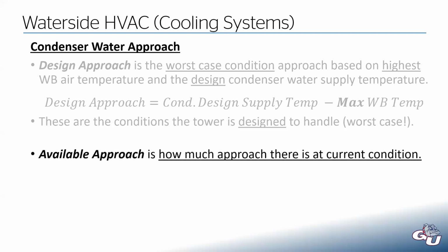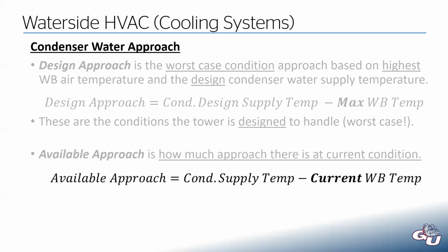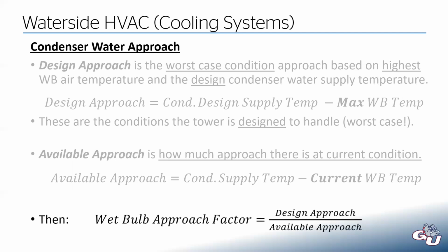The other term, though, is the available approach, which you could describe as how much approach do we have right now at this exact hour, at this current condition. And that's going to be changing all over the place. So our available approach is going to be our condenser supply temperature minus our current wet bulb temperature. So our design approach, worst case condition. Available approach is what do we have right now? Then we have this term called the wet bulb approach factor, which is just your design approach divided by your available approach.